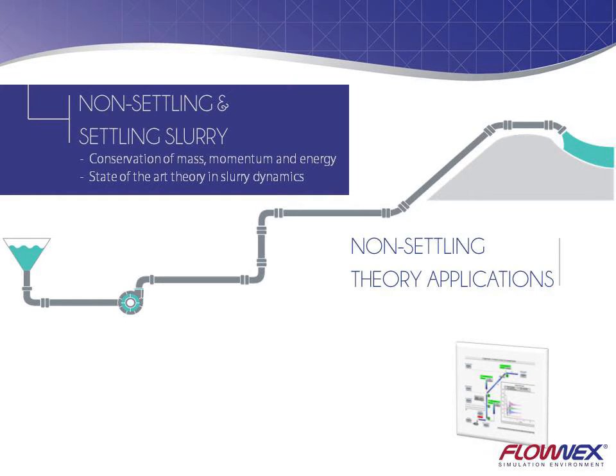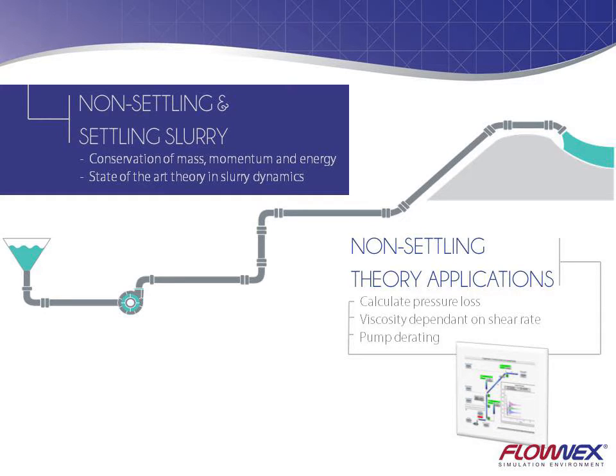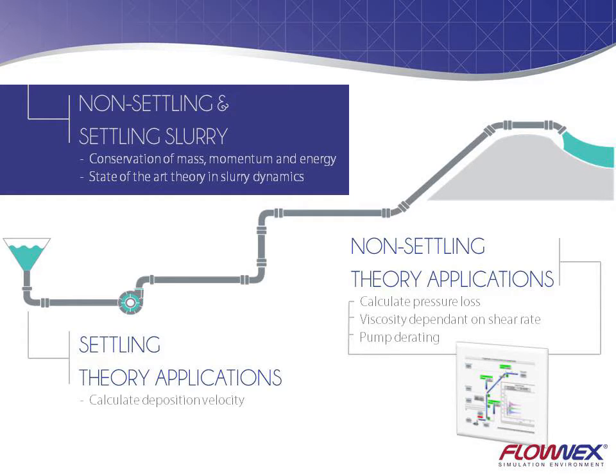Non-settling slurries typically have very fine solid particles in suspension and Flownex incorporates the applicable non-settling pressure loss and shear rate viscosity dependent calculations. The settling slurries typically have larger solid particles that sink out if not supported by a sufficient degree of turbulence. The interaction between these heavier particles and the conveying fluid, as well as the applicable pressure loss calculations, are incorporated in the calculation models.